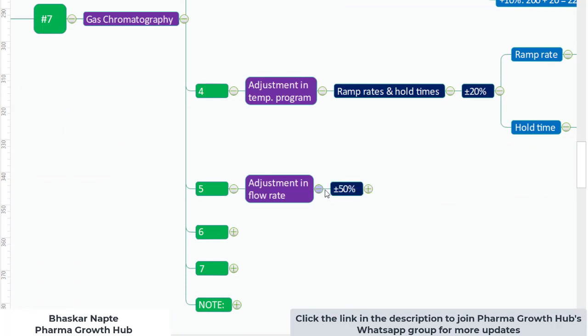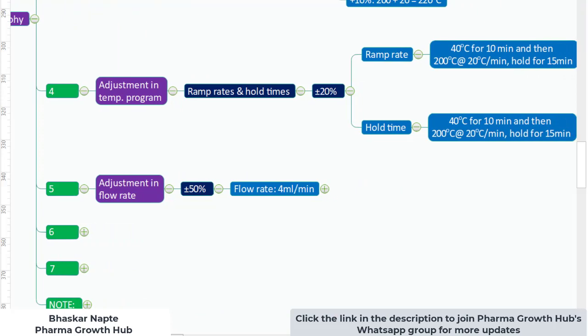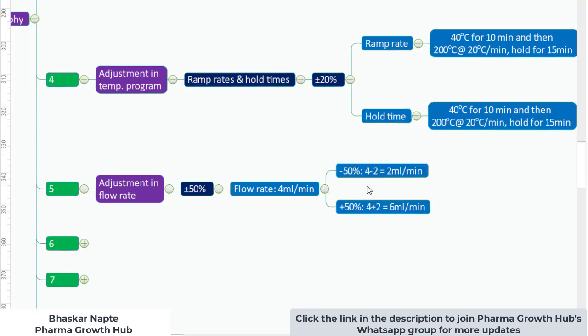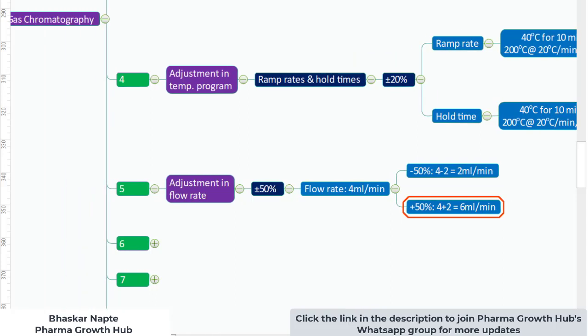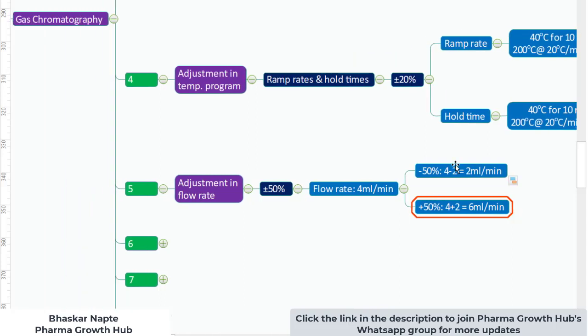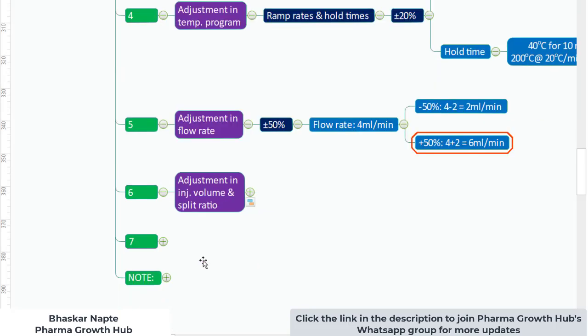Adjustment in flow rate: plus or minus 50% is allowable. For example, if the flow rate of your analytical method is 4 mL/min, minus 50% gives 2 mL/min and plus 50% gives 6 mL/min. So a flow rate from 2 mL/min to 6 mL/min is acceptable.